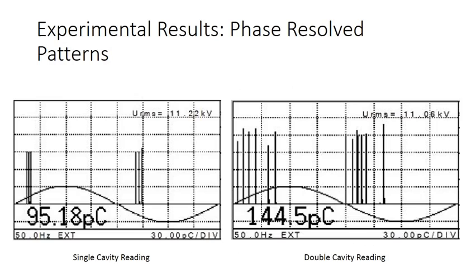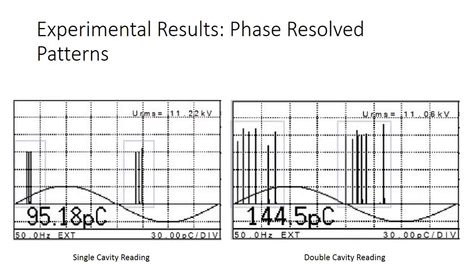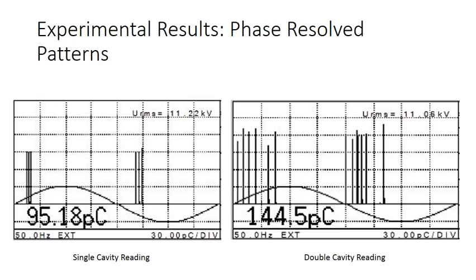The pulses represent the cavity discharge activities for the laboratory samples. The single cavity resulted in fewer charge pulse rates at a distinct position and magnitude.